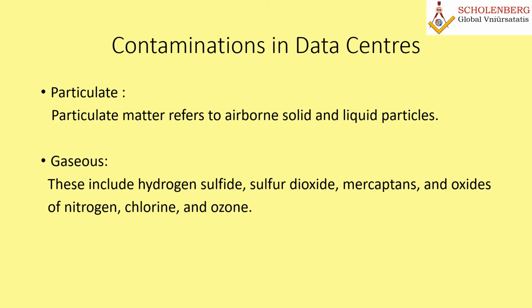They act alone or in synergy with each other or with particulate matter to corrode metallic materials, causing irreversible damage to circuit boards, connectors, integrated circuits, and the other electronic components can be damaged. If datacom facilities serving critical applications happen to be susceptible to gaseous or particulate contamination, the consequences could be devastating. As a result, it is important to address the potential of contamination and mitigate the risk as much as possible, because such factors can result in increased failure rates.